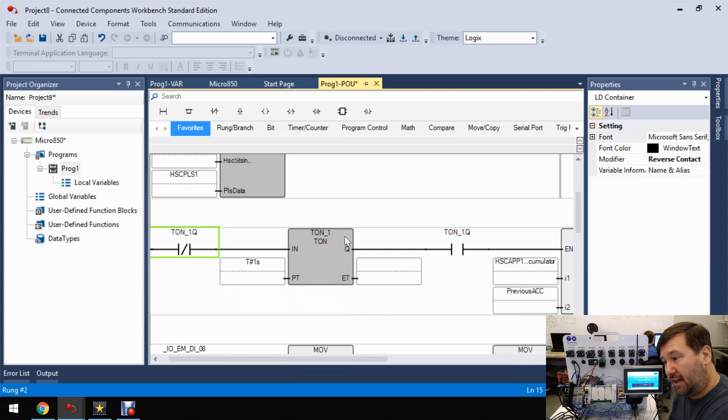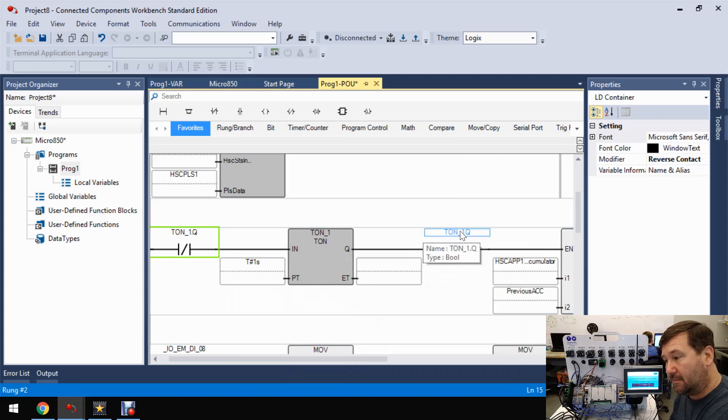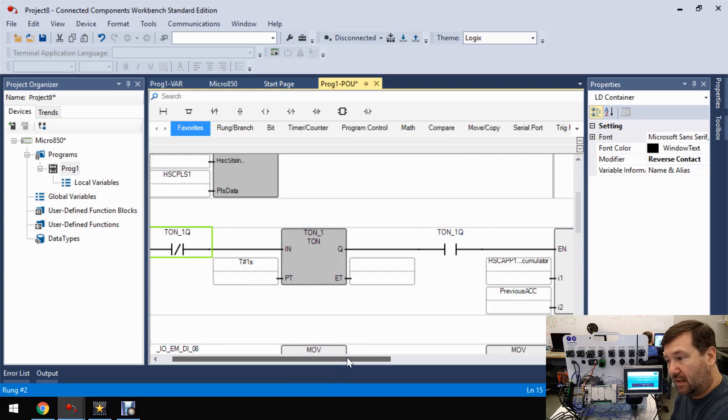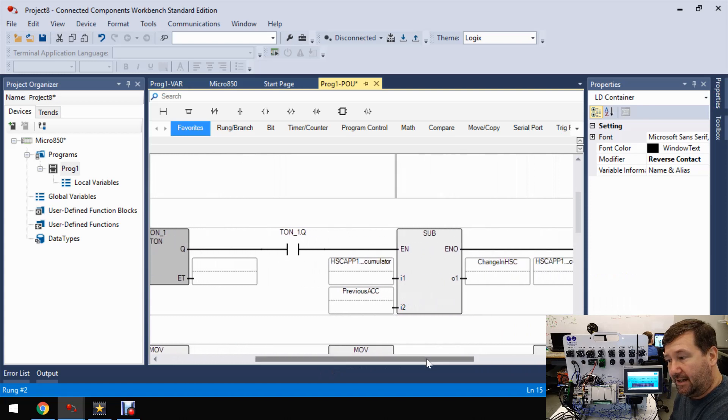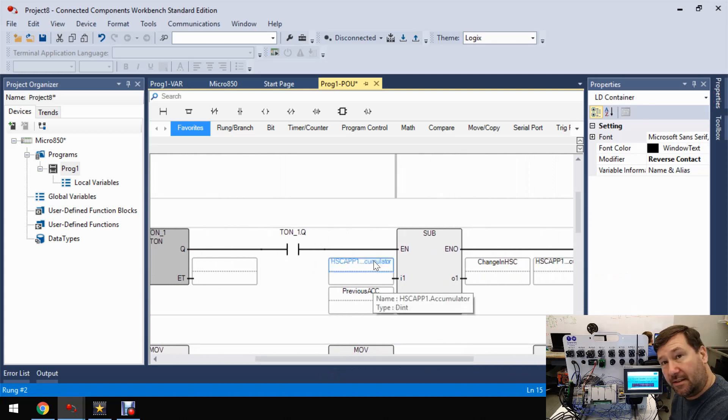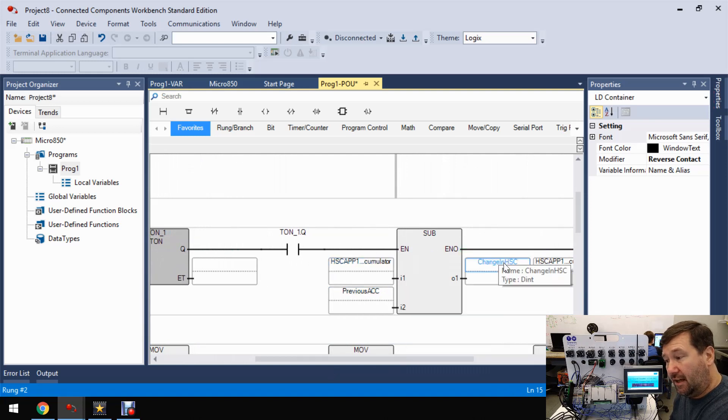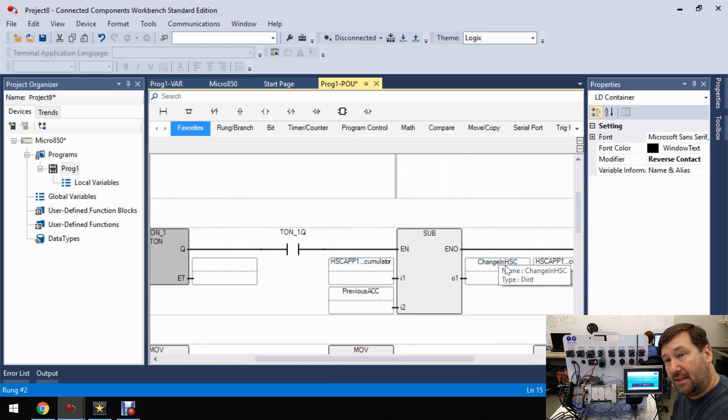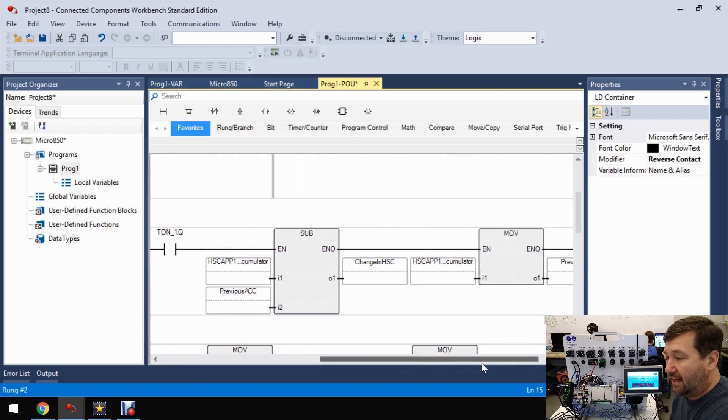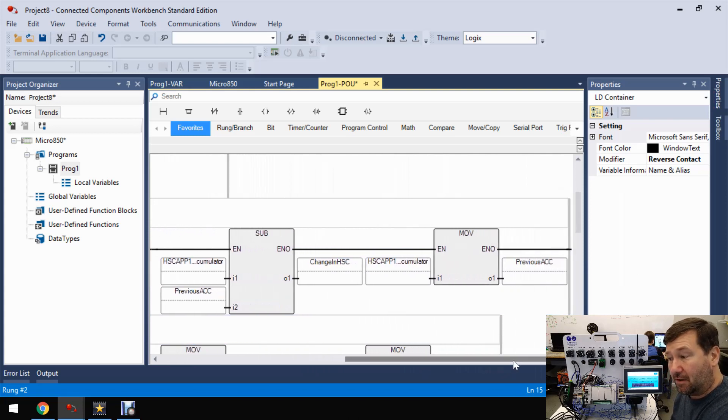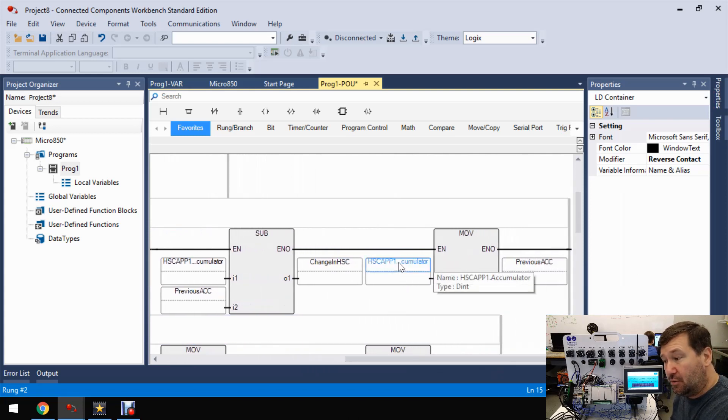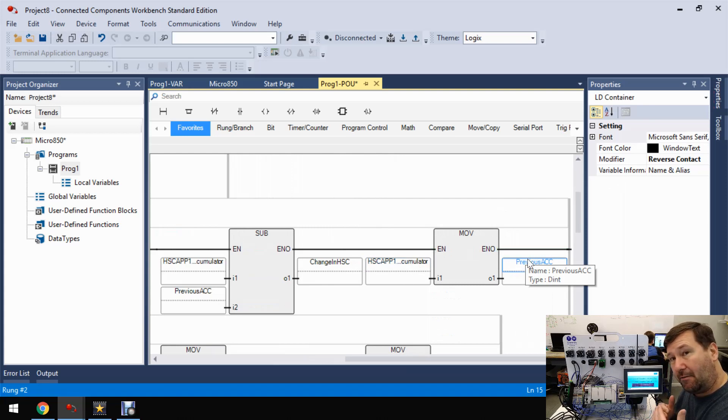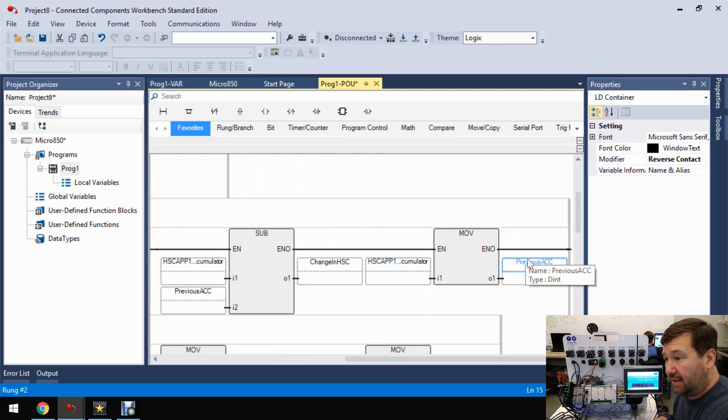And so for that one little scan, this section is going to be true. And it is going to subtract our previous accumulated value from our accumulated value and put it into our change in high speed counter or change in HSC tag. And then finally, we're going to move that accumulator to the previous one. And that way, we get the change over that second.